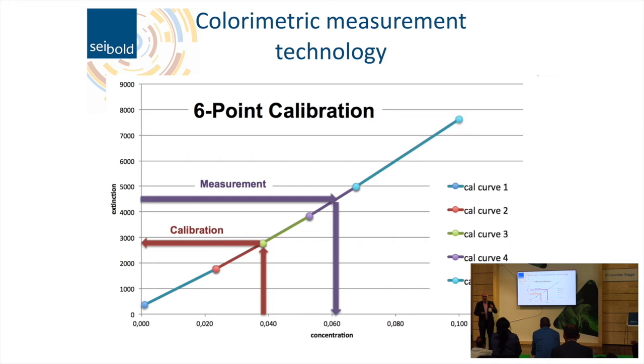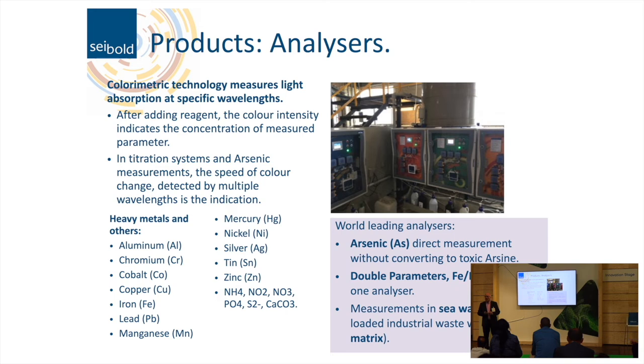A six-point calibration correlates the absorbance value — the color intensity — to concentration. We chose six points because calibration quality is very important for accurate data; you must know if your calibration is performing well or not. Our products cover the whole range of heavy metals, including rare ones such as cadmium, mercury, boron, tin, and others. Our focus is heavy metals, with measurements mostly starting at 1 PPB and going up to hundreds of PPM for specific applications.